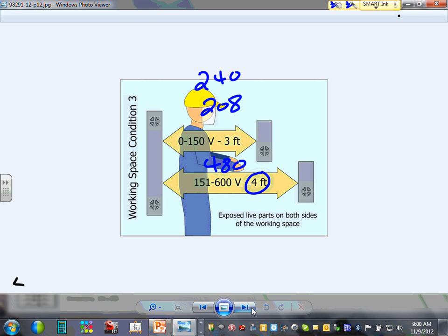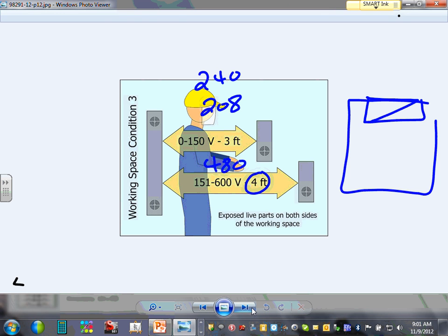That's why a lot of engineers, when you have your panel, the first thing they do, they draw a 4-foot box in the front of the panel, and they say clearances, just 4, regardless. Just start with 4. So if it's 3, you're covered, and if it's 4, you're covered. Cool? So if this is my panel coming in my house here, like you guys did with your friend Chad, here's my panel. And so what they do is they go right in here and they draw a box, and that box would be the width of the panel, the depth of that box would be 4 feet, and they hash it. If you go work in an engineering firm, you'll see it hashed like this. This means that space in front of the panel, do not mess with it. It's a sacred cow. Thumbs up, Chad. We fully understand that one.